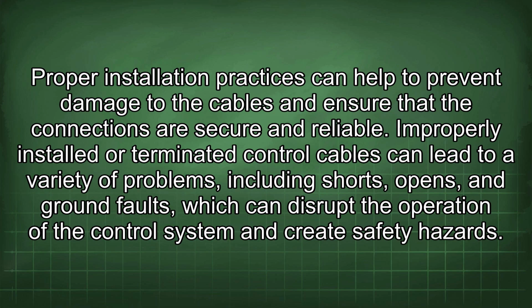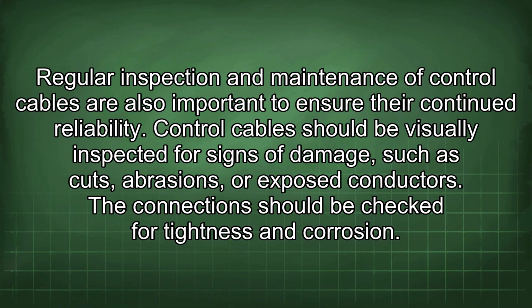Proper installation practices can help to prevent damage to the cables and ensure that the connections are secure and reliable. Improperly installed or terminated control cables can lead to a variety of problems, including shorts, opens, and ground faults, which can disrupt the operation of the control system and create safety hazards. Regular inspection and maintenance of control cables are also important to ensure their continued reliability. Control cables should be visually inspected for signs of damage, such as cuts, abrasions, or exposed conductors. The connections should be checked for tightness and corrosion.